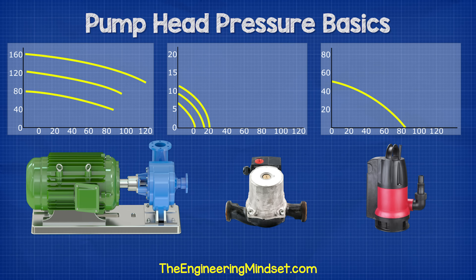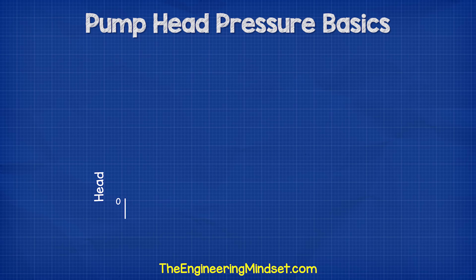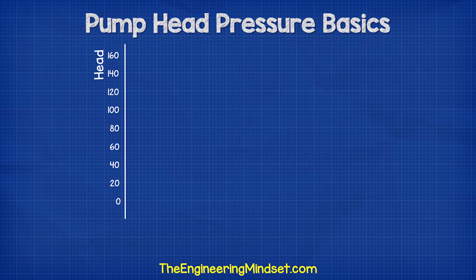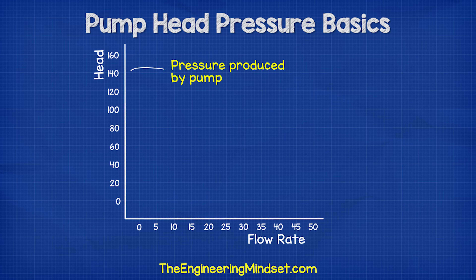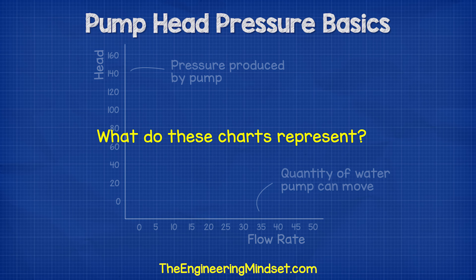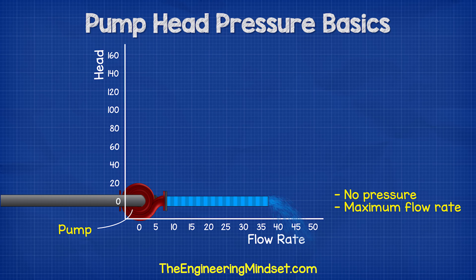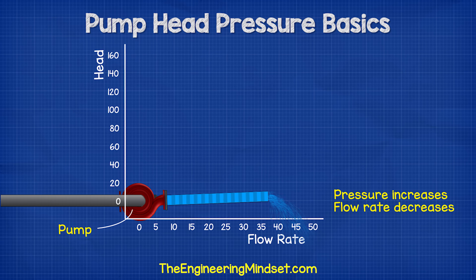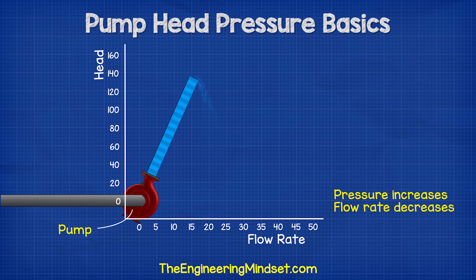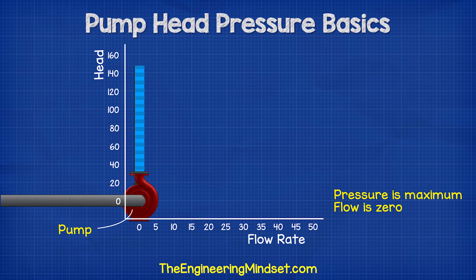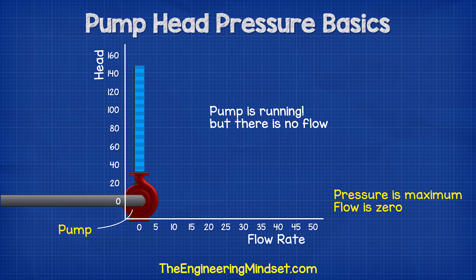Each type of pump has a different chart and the data plotted on them also varies with the model. The first thing we notice is that on the main vertical y-axis we have the head pressure, and on the horizontal x-axis we have the flow rate. The head is pressure and the flow rate is how much water the pump can move. If we turn the pump sideways and connect it to a pipe, the pump is pushing the liquid horizontally so there is no pressure, but the water is flowing at its maximum flow rate. As we slowly rotate the pump towards the vertical position, we see the flow rate decreases but the pressure increases, because it's now pushing against the water and the friction. As we get all the way to the vertical position, there is zero water flowing out of the pump but maximum pressure, as it's using all its energy to push against the water and hold it as high as it possibly can within the pipe.